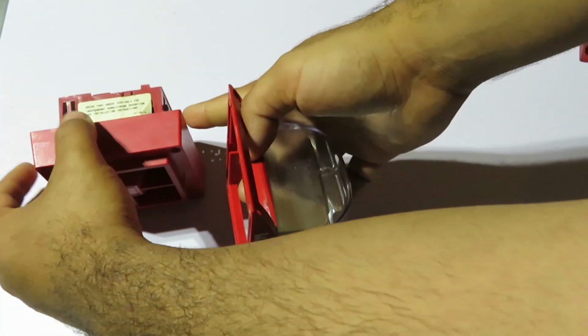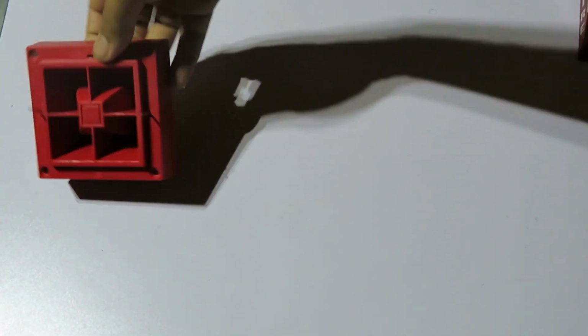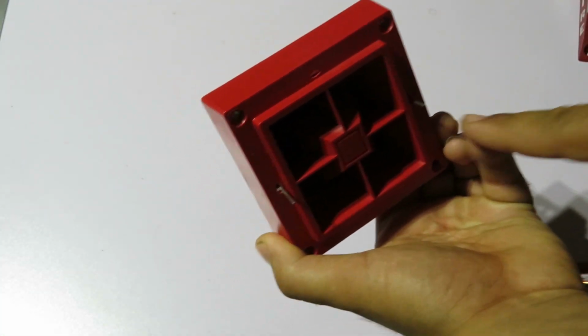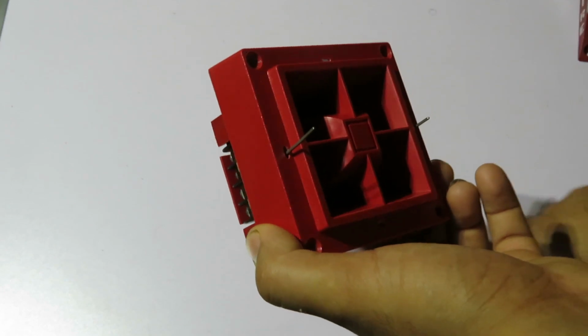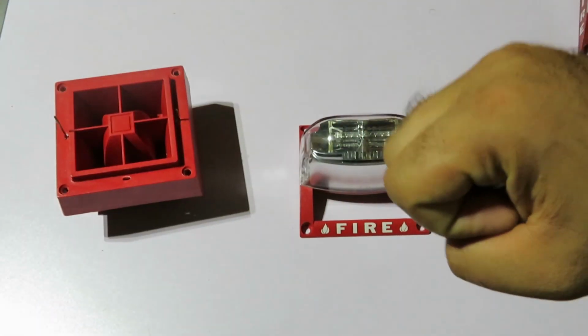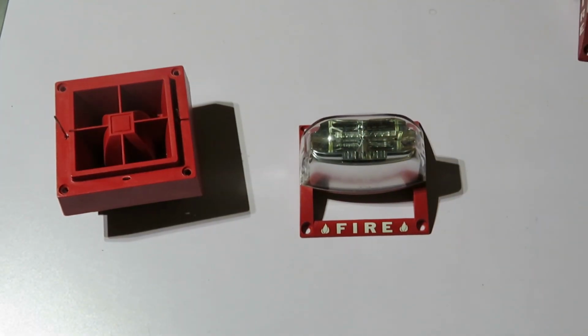What I would advise you to do is, after you pull it off, remember how you pulled it off and sit the device like this, so you don't end up wiring it backward. But it fell down, whatever. So it's just going to be this way. But make sure you remember. And if you don't remember somehow, the right side is red, the other side is black. You need to remember it, because if you wire it backward, the strobe won't flash and you're going to think, oh, I broke it. So always remember that.